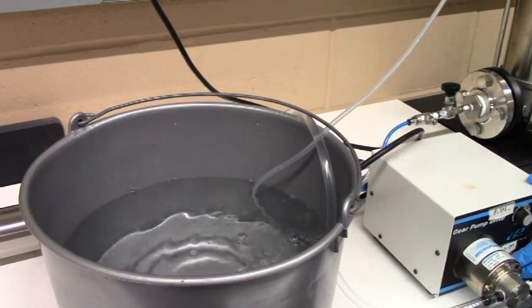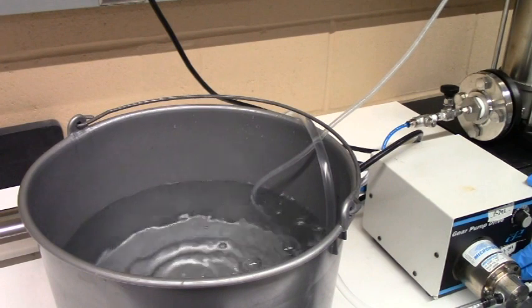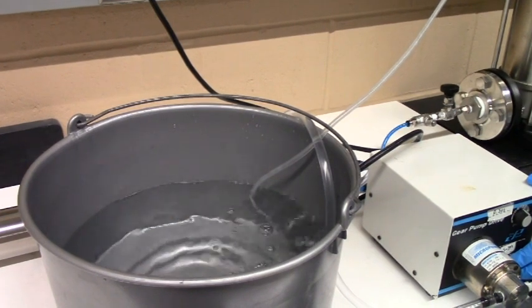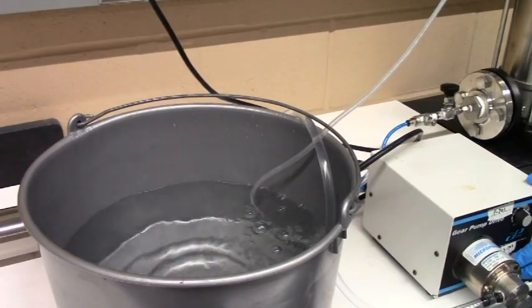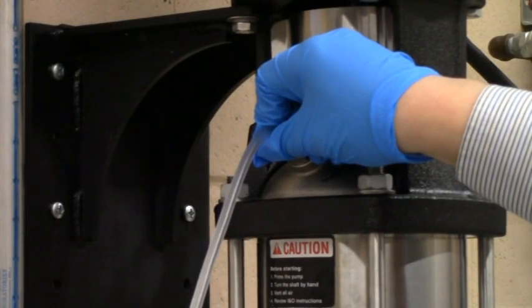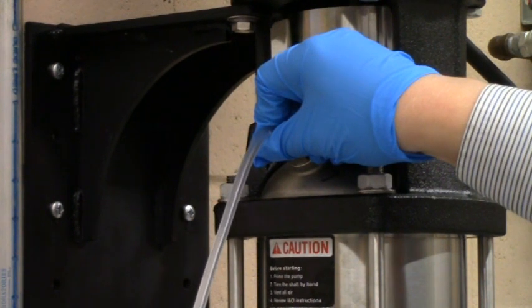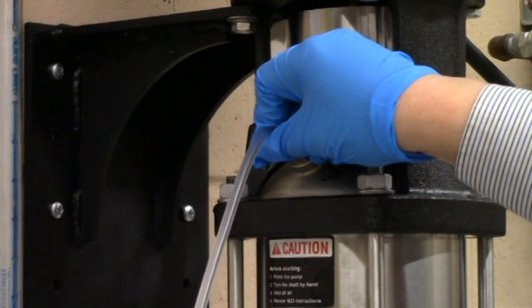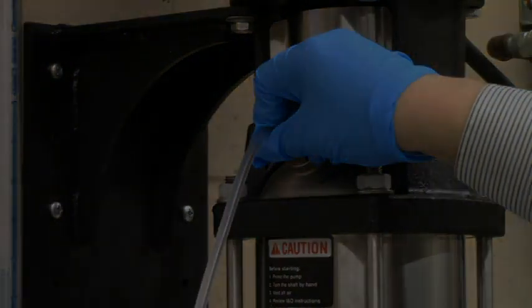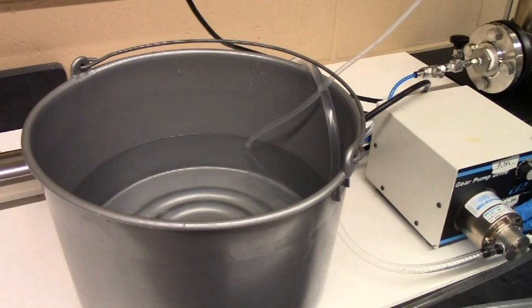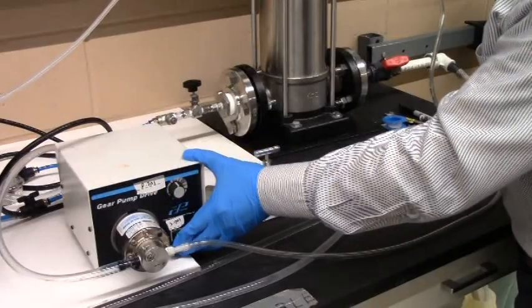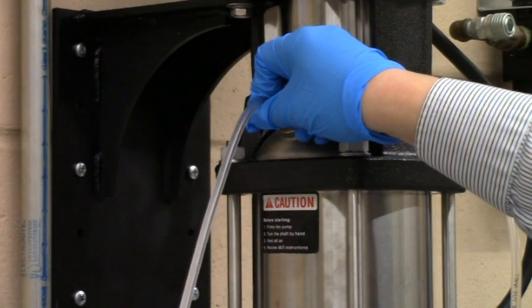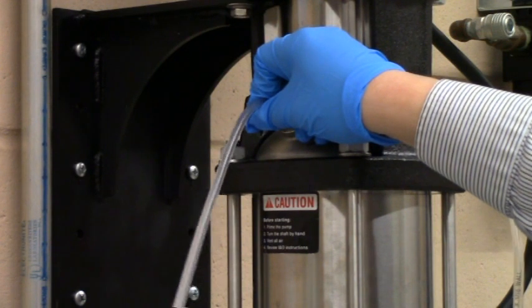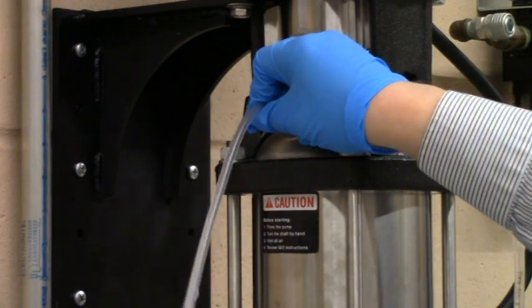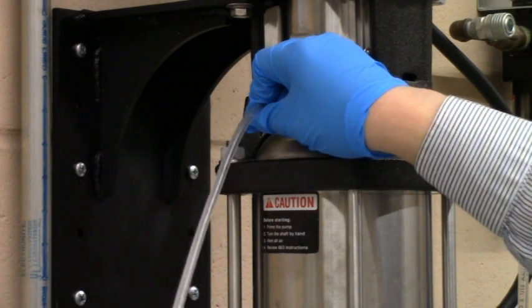As you fill up the centrifugal pump with water, initially you will see bubbles coming out of the end of the small tube in the bucket. After a while, when the centrifugal pump becomes full of water, you will see water coming out of the prime outlet through the small tube. Wait until water flows steadily in the small tube and no bubbles come out. Then turn off the gear pump. Keep pressing the small tube into the prime outlet. The residual pressure will push some water out. Hold the tube there until nothing comes out and it becomes quiet.